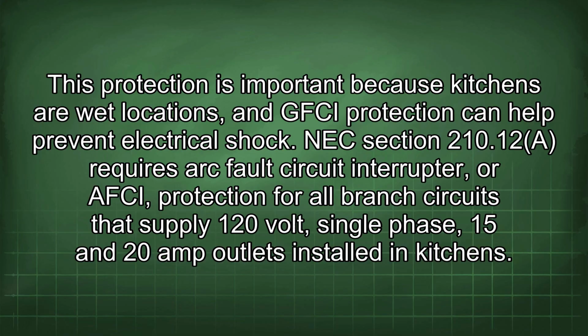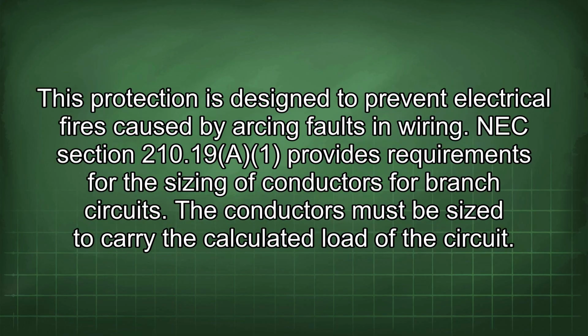NEC section 210.12 requires arc fault circuit interrupter, or AFCI, protection for all branch circuits that supply 120 volt, single phase, 15 and 20 amp outlets installed in kitchens. This protection is designed to prevent electrical fires caused by arcing faults in wiring.